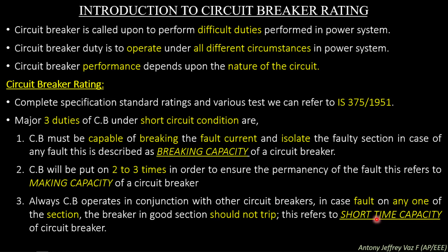If you see a power grid, there will be several sections and several grid areas. For example, in our town itself, we will have several sections: the north section, south section, east section and west section. If a fault is found in the north section of the town, then only the north section should be isolated. The south, east and west sections should not be isolated, because the fault is occurring only in the north section. So the circuit breaker should have a short time capacity to carry the fault current, so that the north section circuit breaker will trip and the other section circuit breakers will wait till the north section circuit breaker clears the fault. This is referred to as short time capacity.